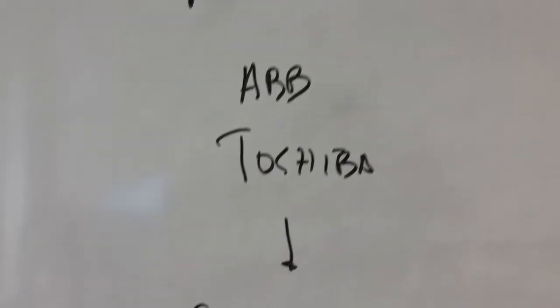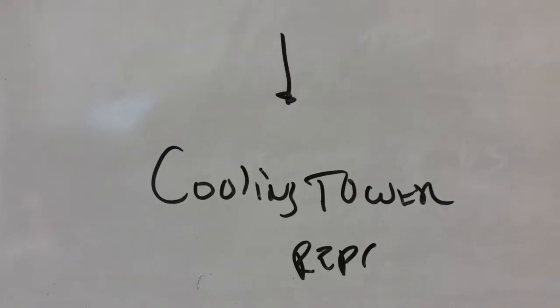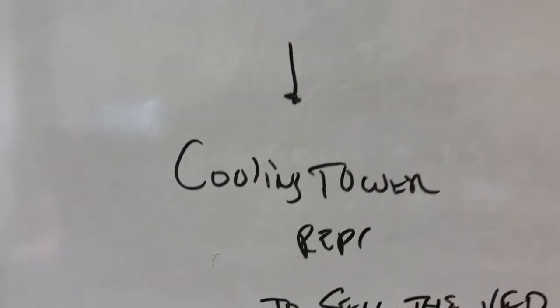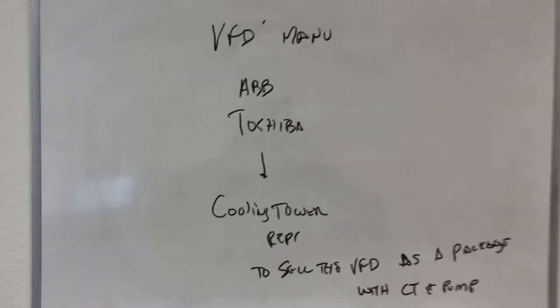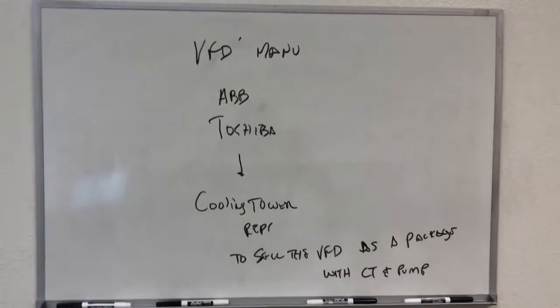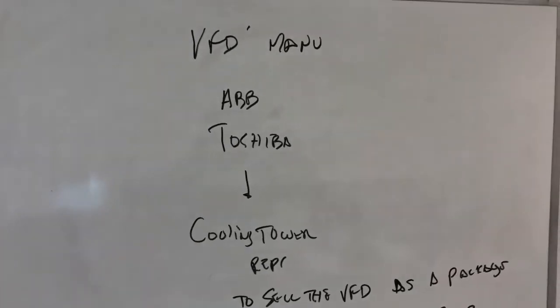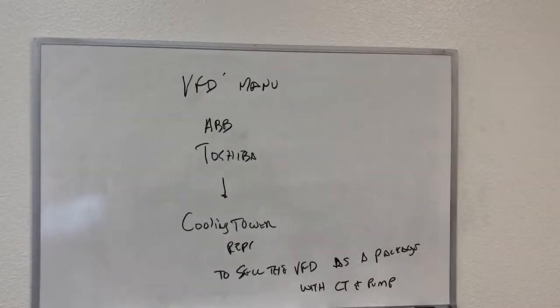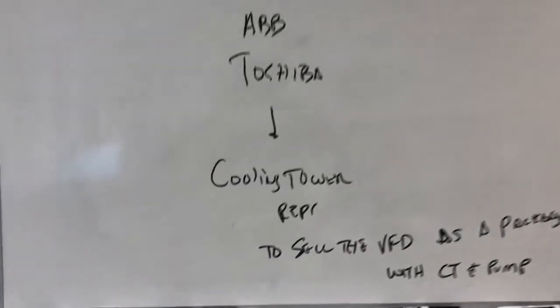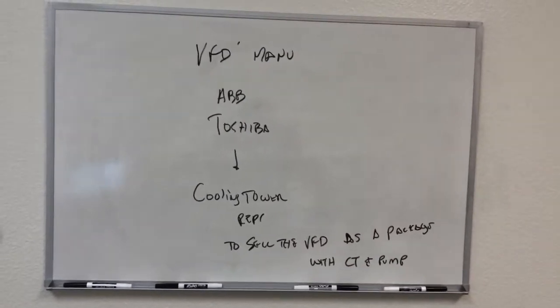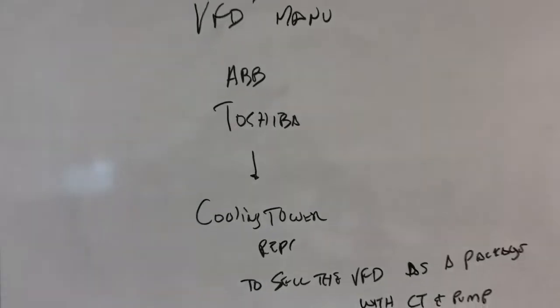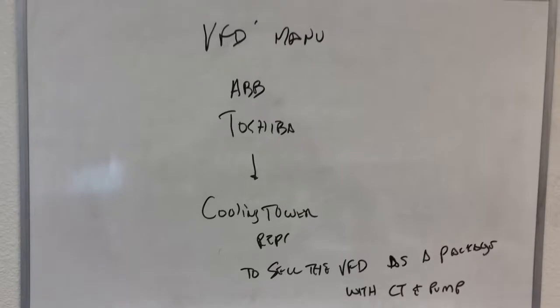Then the VFD manufacturers, ABB, Toshiba, and others, go to cooling tower representatives, the people who sell cooling towers and represent the big cooling tower and pump manufacturers, to sell the VFD as a package with the cooling towers and pumps. So now we've got an electrical piece of equipment, clearly electrical, found in the mechanical spec and being sold by people who sell mechanical equipment, not electrical wholesalers. Cooling tower reps know absolutely nothing about electrical equipment.